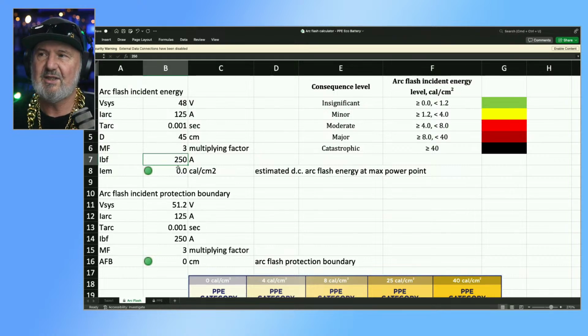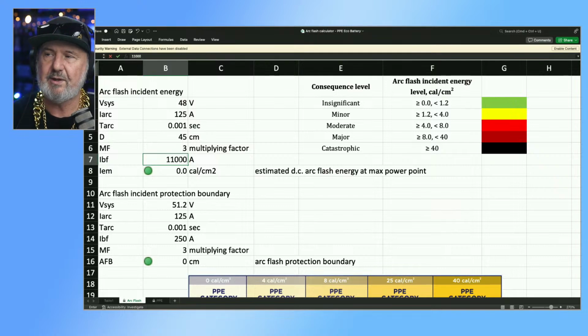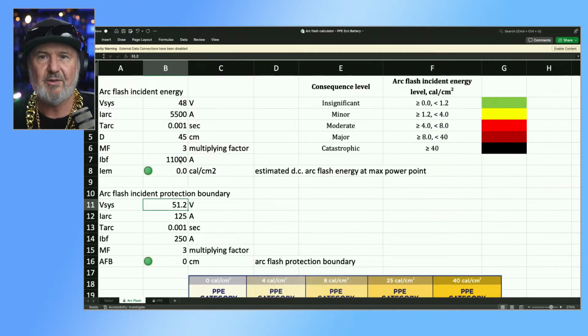But let's say this is a 1000 amp hour lead acid battery, pretty popular once upon a time for off-grid, and it'll have a bolted fault current of about 11,000 amps. Now that sounds ridiculously high, but that's one of the amazing things about lead acid batteries, they're extremely high prospective fault current. The arcing current, IARC, is half that.